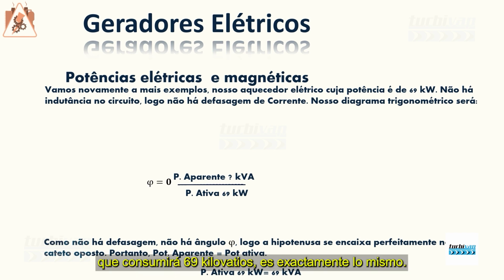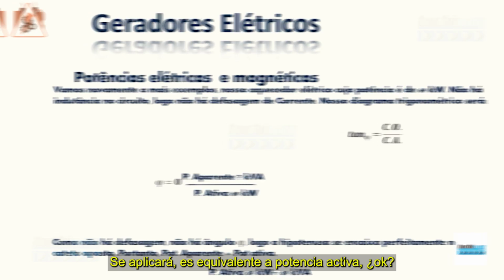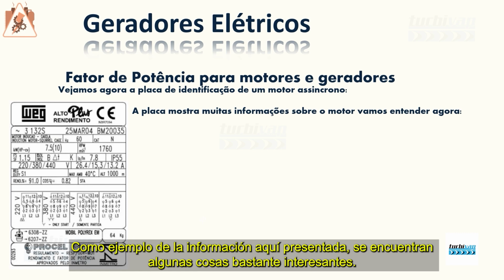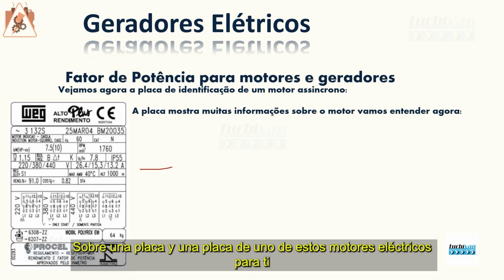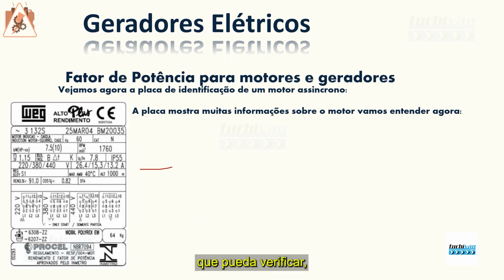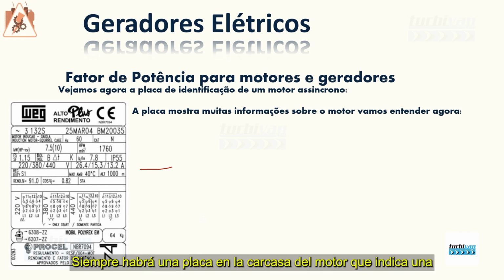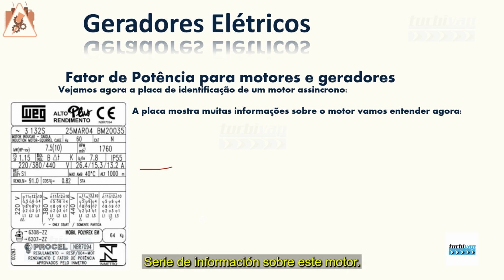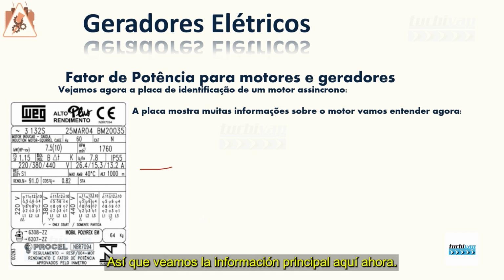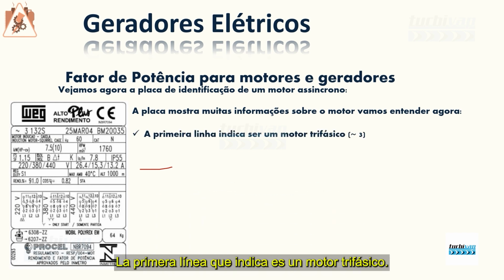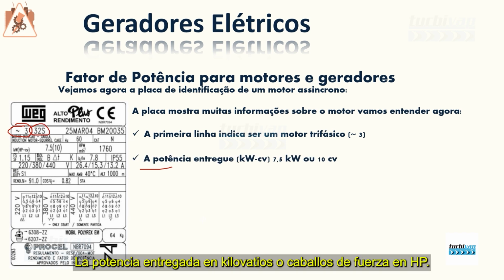As an example, here is some quite interesting information about the nameplate of one of these electric motors that you can verify. There will always be a plate on the engine casing indicating a series of information about this engine. So let's see the main information now. The first line indicates it is a 3-phase motor. This here is the symbol of a 3-phase motor. This here is the engine model. The power delivered in kilowatts or horsepower in HP is 7.5 kilowatts or 10 horsepower.